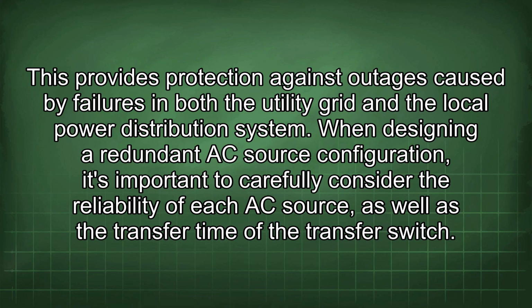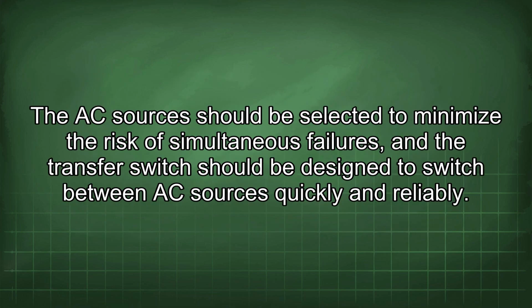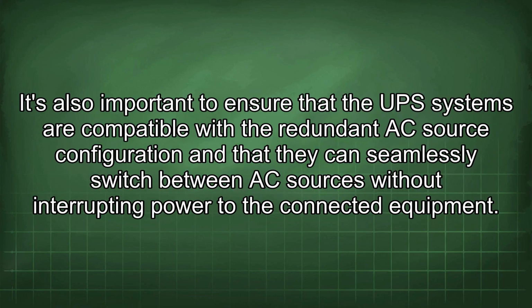When designing a redundant AC source configuration, it's important to carefully consider the reliability of each AC source as well as the transfer time of the transfer switch. The AC sources should be selected to minimize the risk of simultaneous failures, and the transfer switch should be designed to switch between AC sources quickly and reliably. It's also important to ensure that the UPS systems are compatible with the redundant AC source configuration and that they can seamlessly switch between AC sources without interrupting power to the connected equipment.